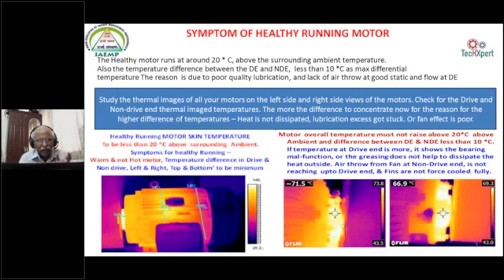So the difference between driven and non-driven end temperature has to be around 10 degrees. If it is more than 10 degrees, or more than 20 degrees, then let us see why it is happening. You can see the right side images. The temperature at the bearing is going more and more, and because of that, the skin temperature is also going more than 70.